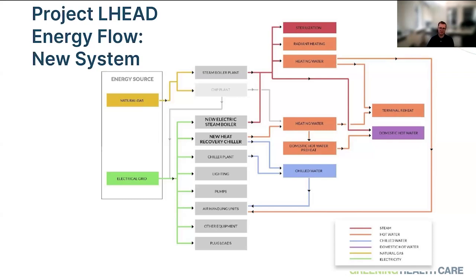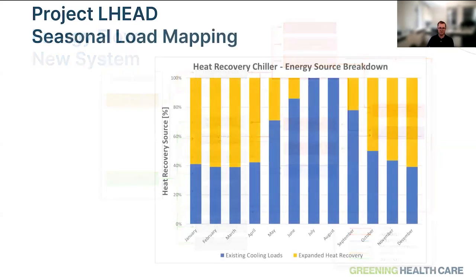And then the second challenge is finding ways to load it year round. That's where opportunities like exhaust heat recovery, or recovering from MRI loads and these types of equipment loads, can generate the base load cooling year round to load the heat recovery chiller. And then going into existing facilities, the challenge is to understand how the two hydronic networks are functioning. Ryan gave a good example for his hospital in Port Alberni, where a small misunderstanding about the hydronic network was costing them savings, and a relatively simple fix benefited the hospital immensely. So understanding how the hydronic networks are operating is pretty important to adding a heat recovery chiller to an existing facility.